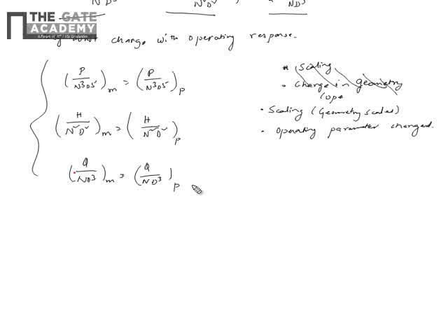Just like we had specific speed for the pump, here also in the turbine literature a specific speed for the turbine is defined. It is a function of your cp and ch, and finally it comes out in this way. As this is another non-dimensional number, a function of two non-dimensional numbers, the specific speed is constant when you are scaling or when operating performance is the same.